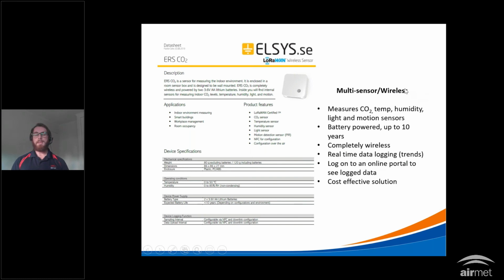It supports NFC, near field communications, via a smartphone application. This application is password protected by default, configured by our department. The sensors utilize an ABC algorithm, or automatic baseline calibration function. This is best supported in applications where areas are not occupied all the time and have good air circulation. This function can also be disabled if the area is of specific concern.